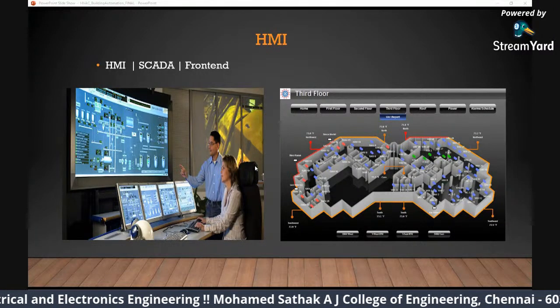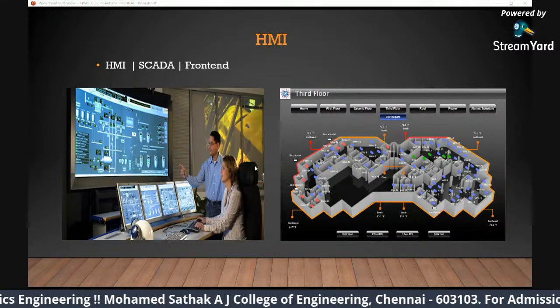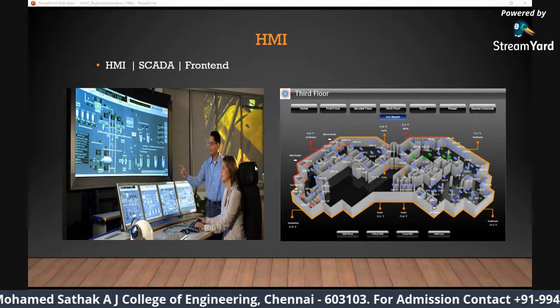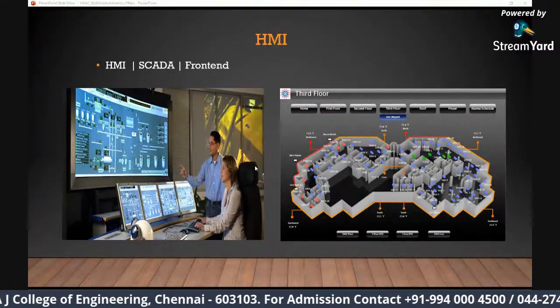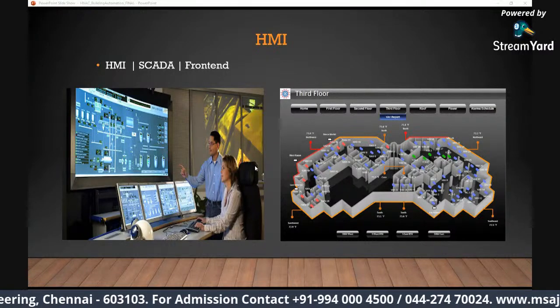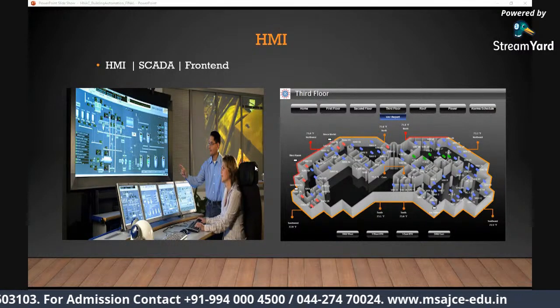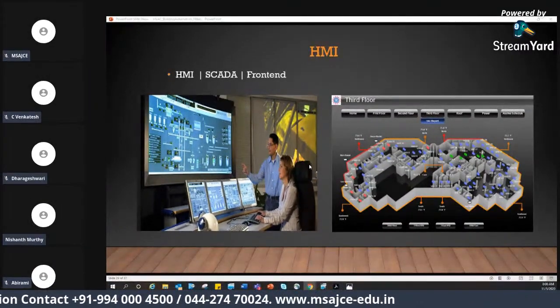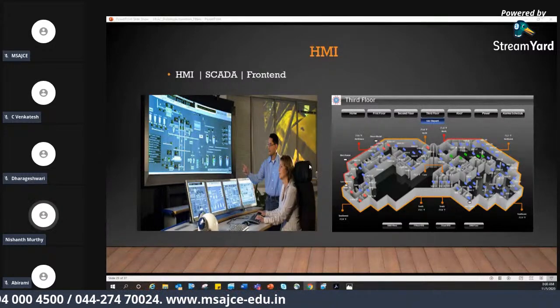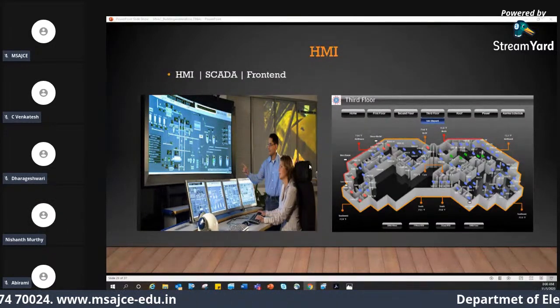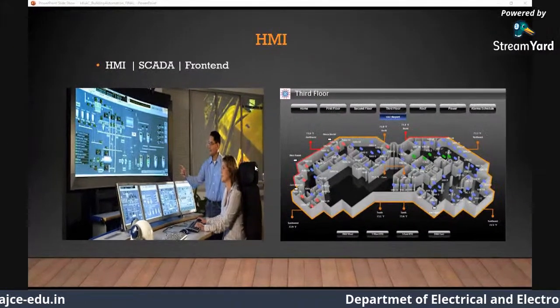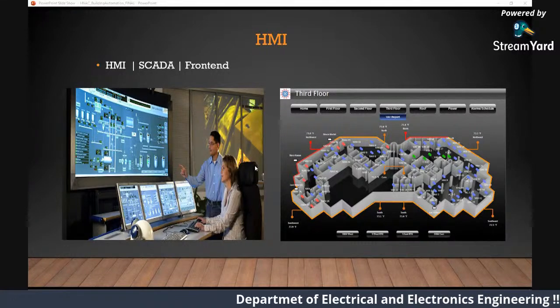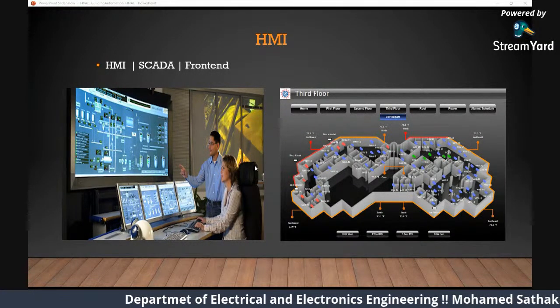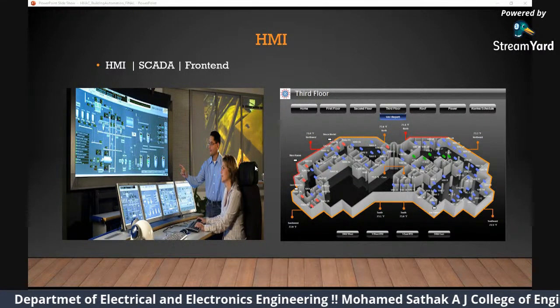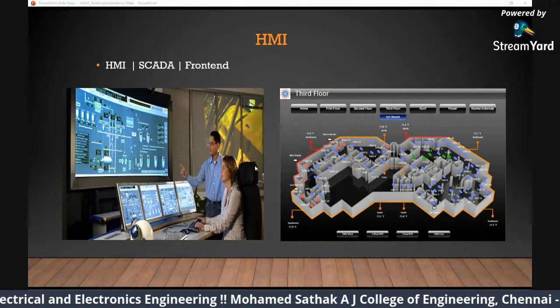So they cannot go to an individual room to monitor the temperature control. Let's say someone in a room on the sixth floor calls up the control room and says it's too hot, there is fire inside. Everything will be monitored from the control room through the front end. So your front end is very important when it comes to operator and monitor. They can turn on a fan, pump, valve, damper. They can reduce the hot temperature in a room. They can reduce the flow, whatever they can control from the front end.